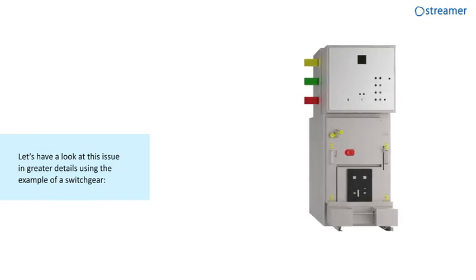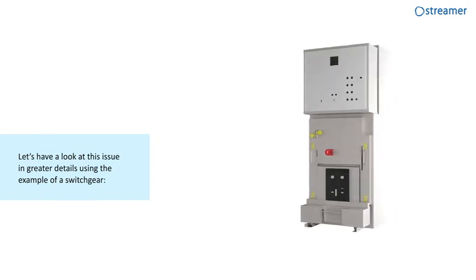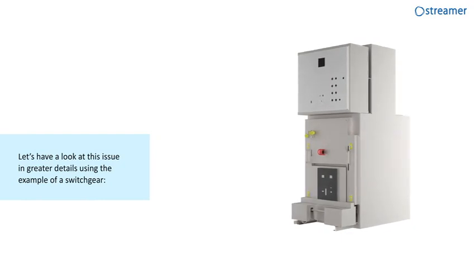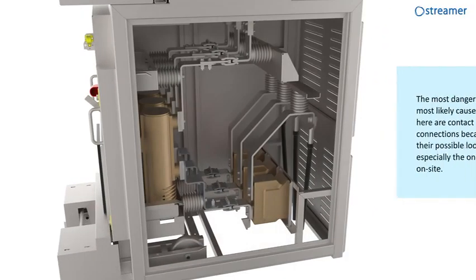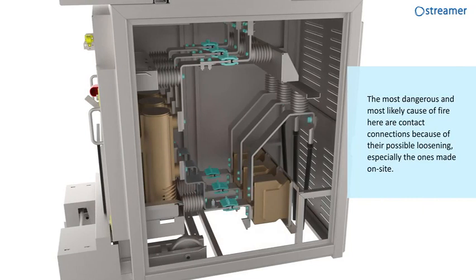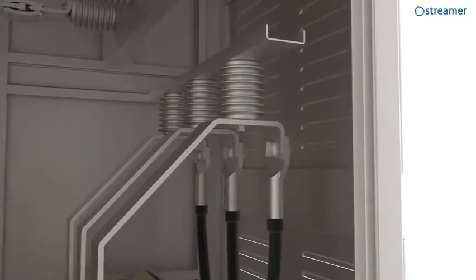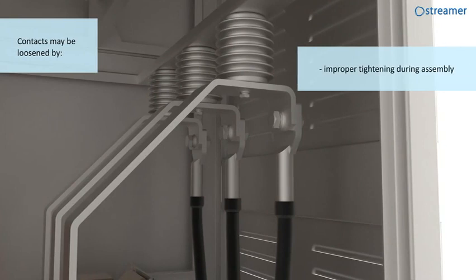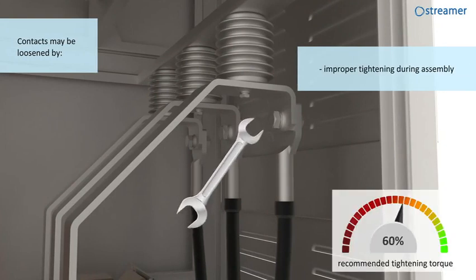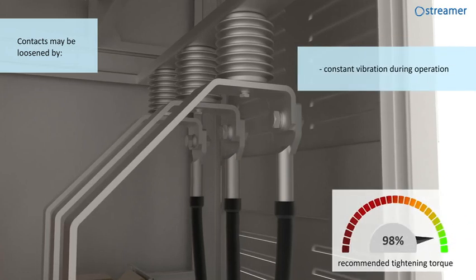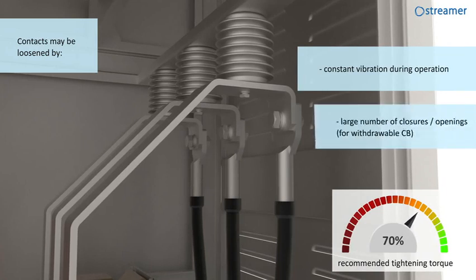Let's have a look at this issue in greater detail using the example of a switchgear. The most dangerous and most likely cause of fire here, as with any MV or LV equipment, are contact connections because of their possible loosening, especially the ones made on site.